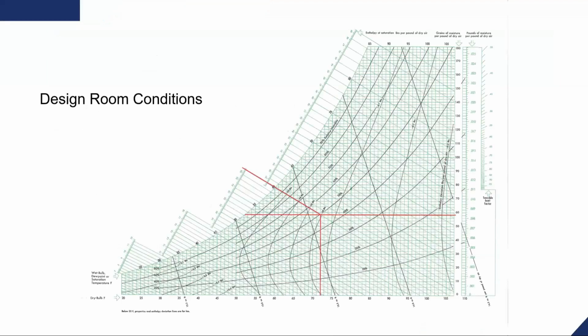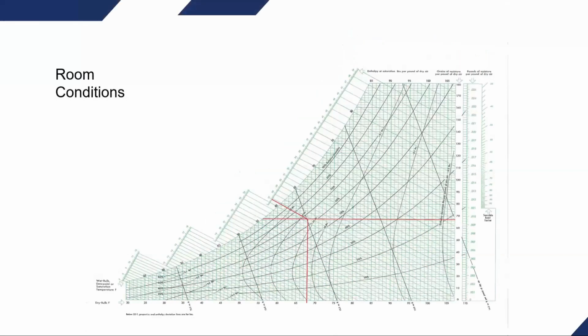So typically you want a design condition of about 70 degrees, 50% relative humidity, give or take a couple of degrees. That's typically where we want everything to be. We were way off from this. Our room conditions in this particular space were 68 degrees and 65% relative humidity.